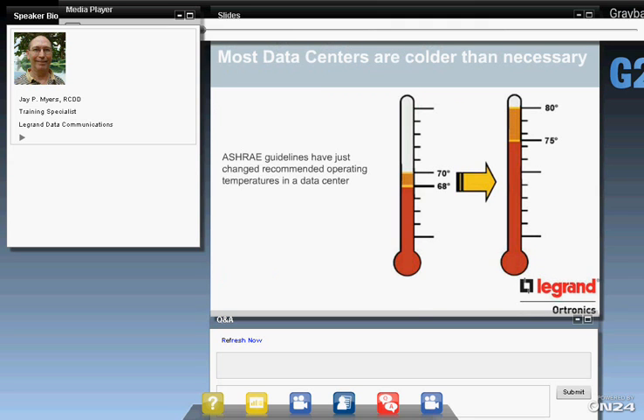Now, ASHRAE, who's acknowledged as the expert in air conditioning, has, over the last few years, dramatically changed their recommendations for operating temperatures in data centers. Their earlier recommendation was down to 68 degrees, pretty cool. But they have recently raised that up to 80 degrees. And that's a very dramatic difference in the amount of cooling required, and it makes possible huge savings. They are acknowledged and recognized as the experts here. So even if that seems strange, I think it's pretty safe to rely on their recommendation.